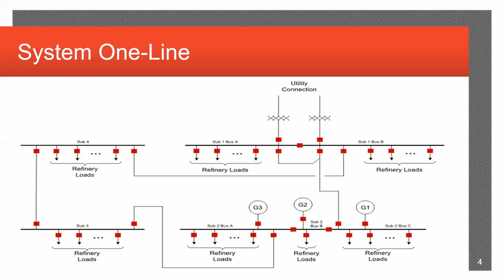There's another question that ties into the previous one: how close were your simulation results to the actual testing? They were identical. Very identical. What was the programming language used in the controller? The controller was an SEL 2411, and we were using SEL logic programming, which is specific to SEL IEDs.